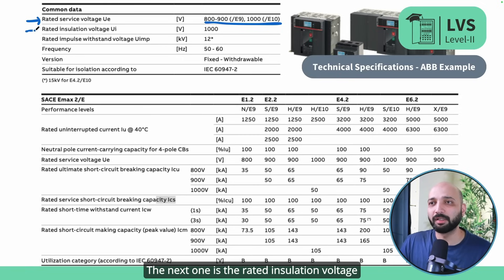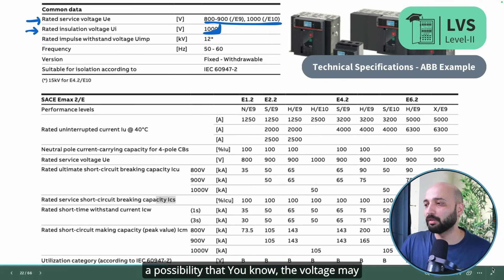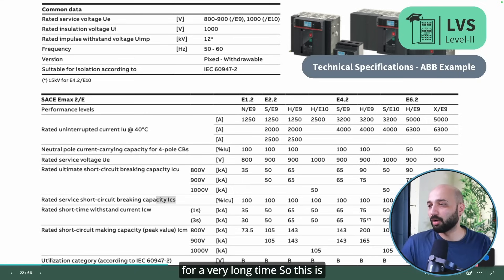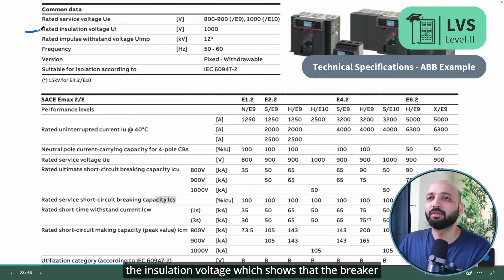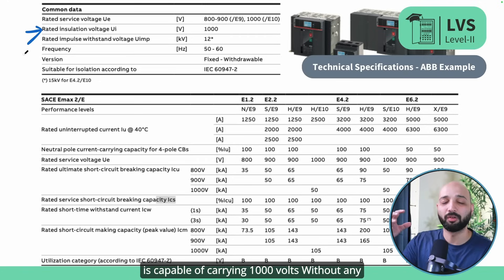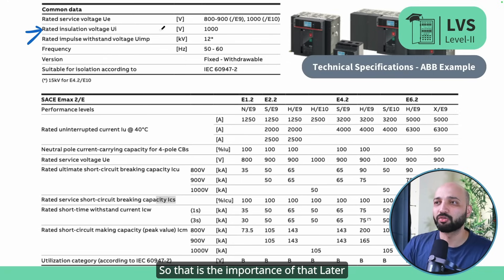The next parameter is the rated insulation voltage, Ui, which is mentioned here as 1000 volts. There is a possibility that voltage may rise in the system and stay there for a very long time. This insulation voltage shows that the breaker is capable of carrying 1000 volts without any problem in such scenarios.